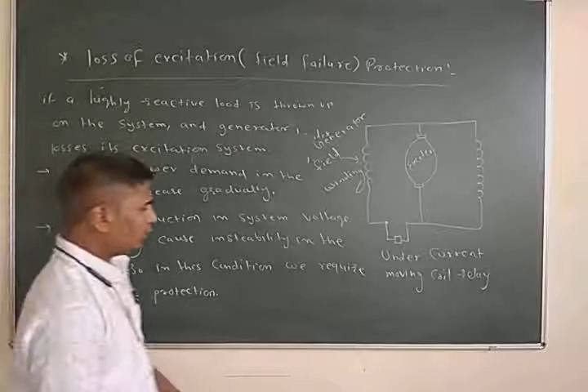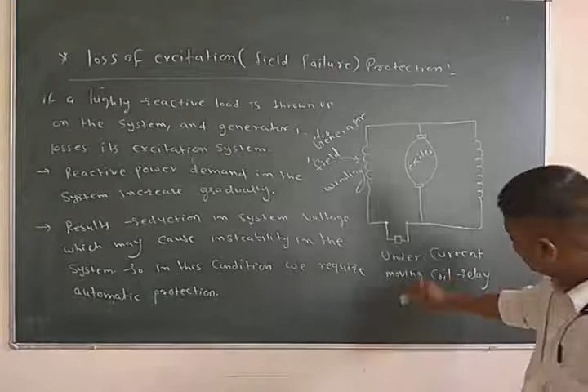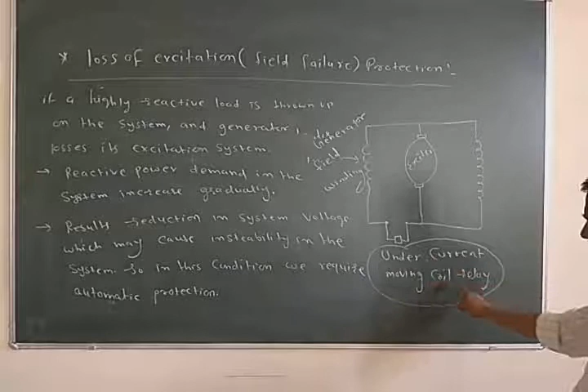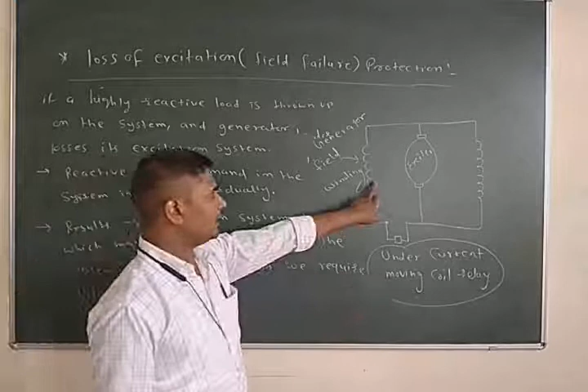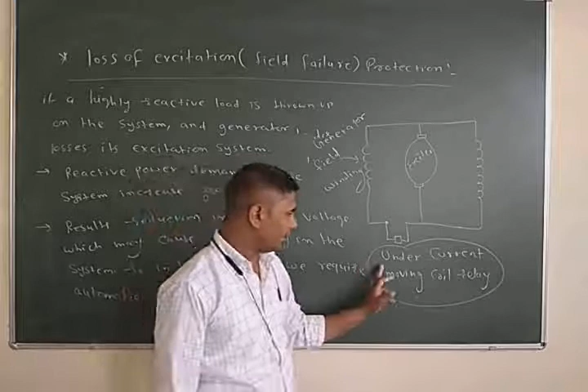Now to provide protection against loss of excitation, first of all, we can use an undercurrent moving coil relay. For protection against failure of the excitation system, we can use an undercurrent moving coil relay. From the name, the undercurrent moving coil relay operates when the current in the field circuit of the generator is less than its rated value.